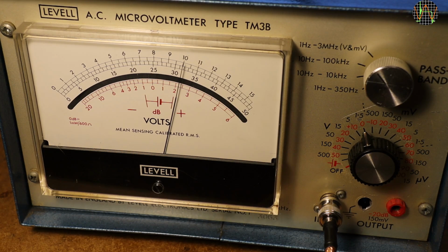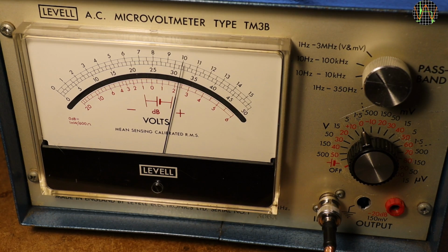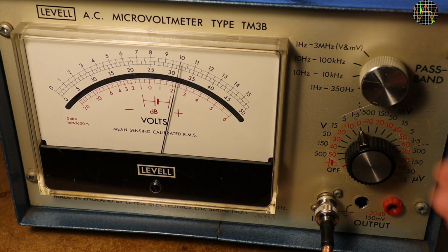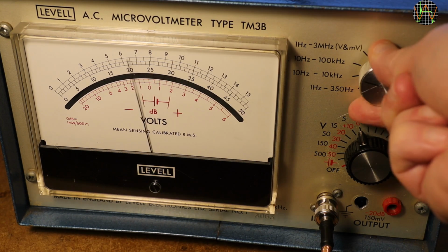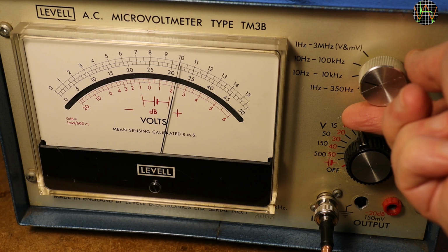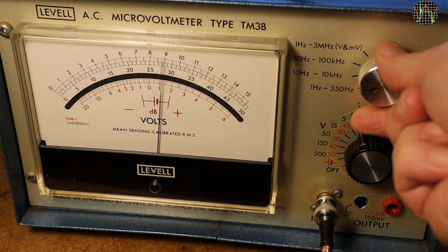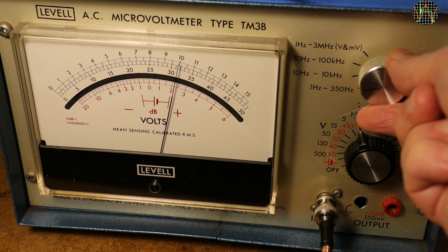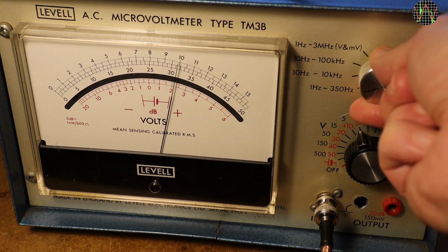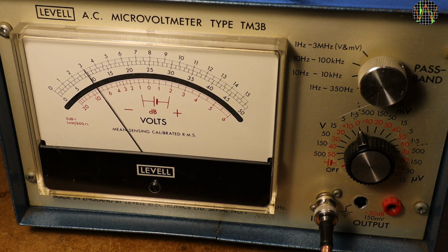I am feeding an AC voltage of 1 volt at 1 kHz, and the meter is currently in the widest bandwidth setting of 1 Hz to 3 MHz, which is the only setting in a TM3A. But in the TM3B I can select a more narrow bandwidth of 10 Hz to 100 kHz. Predictably, this has no discernible effect on a 1 kHz signal. But selecting the next narrower setting of 10 Hz to 10 kHz makes the needle go a tiny bit below 10. And as expected, on the most restrictive setting of 350 Hz, the 1 kHz signal drops massively.